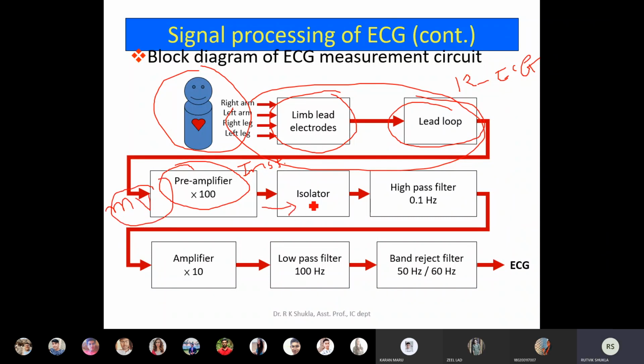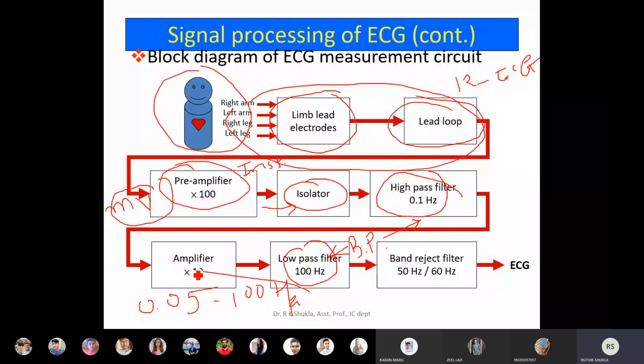That signal goes to the isolator. Isolator is essential for isolating the patient side and the machine side. Then we have a combination of high pass filter and low pass filter, which makes a band pass filter, which allows the signal of interest only. As we have seen, the ECG generally ranges from 0.05 hertz to 150 hertz or somewhere around 100 hertz. This is the frequency range of ECG. So we are only interested in the signal which comes in this particular range. Anything below 0.05, anything above 100 or 150, has to be rejected by the particular filter. Then we have a main amplifier which provides a gain of 10.